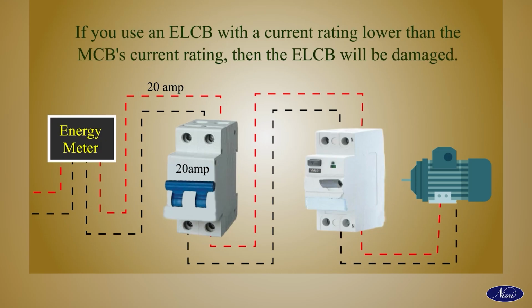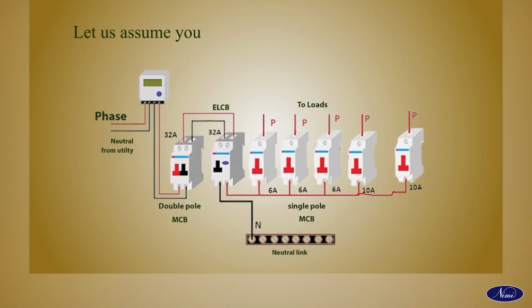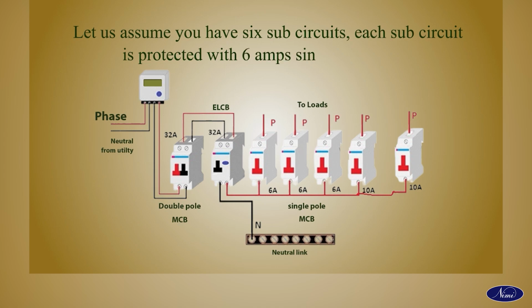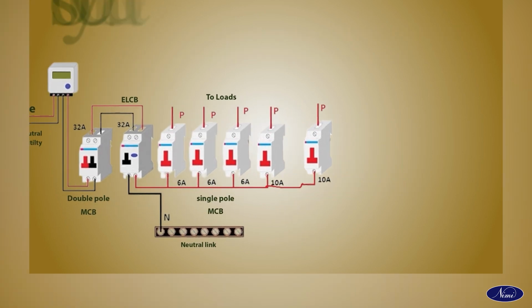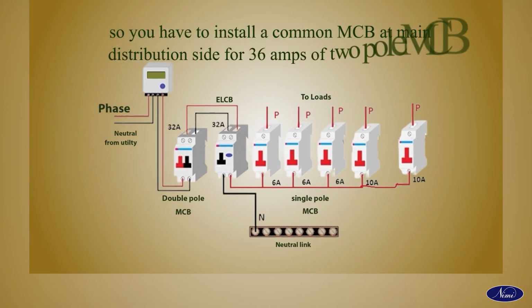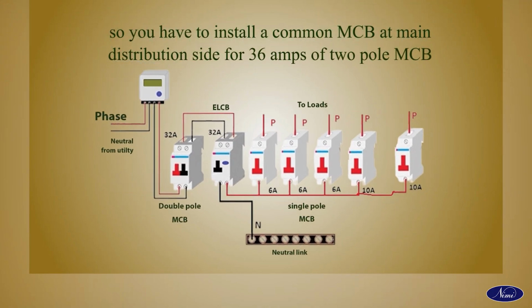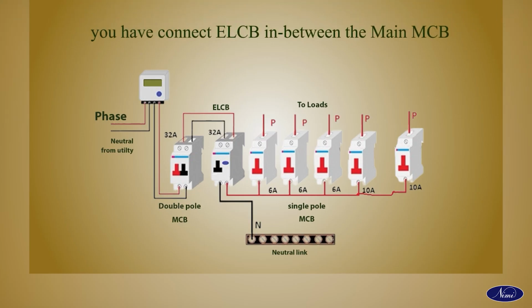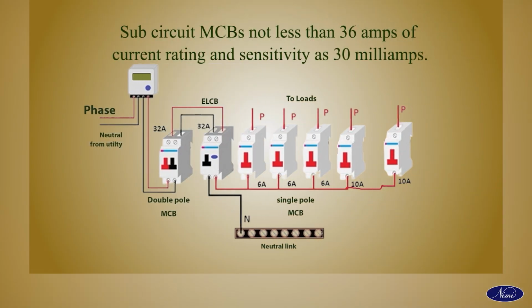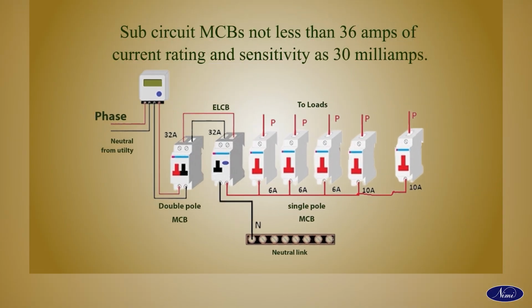Let us assume you have 6 sub-circuits. Each sub-circuit is protected with a 6 amp single-pole MCB. So you have to install a common MCB at the main distribution side of 36 amps, 2-pole MCB. Then you have to connect an ELCB in between the main MCB and sub-circuit MCBs, not less than 36 amps of current rating and sensitivity as 30 milliamps.